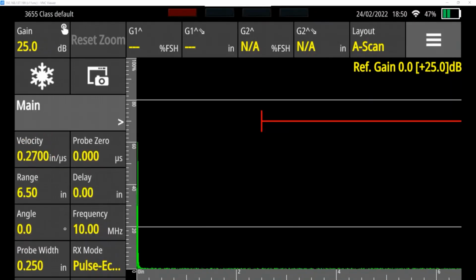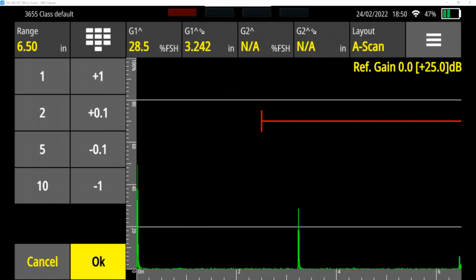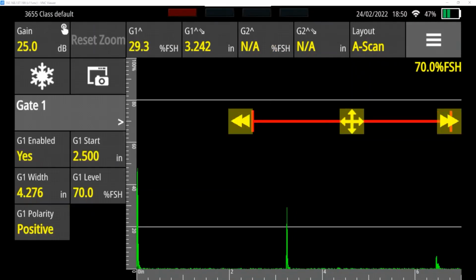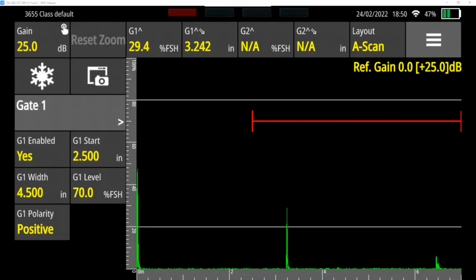So back to me. First, I'm probably going to have to set my gain. We can see this is a much taller block. Actually, I'm going to change my range to 7 inches so that it shows up. This is a much taller block, and so I want to get a signal. The larger the material, the higher the gain, right? It's going to take more energy, and you have to turn up the probe's listening ability to see a weaker signal because the signal is being attenuated more as it travels through the block.